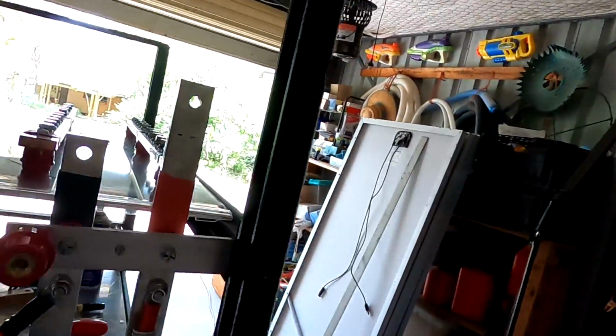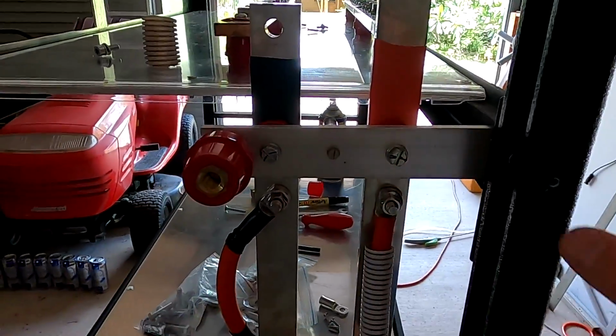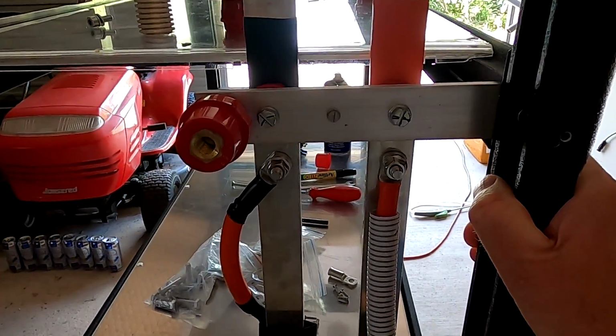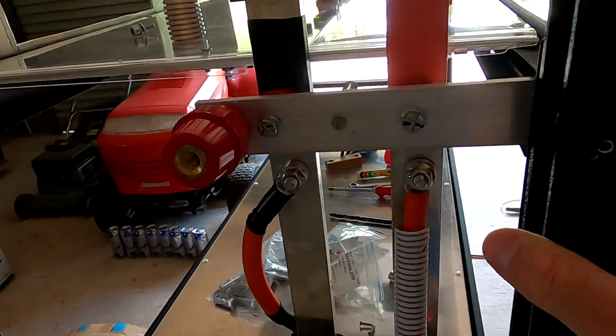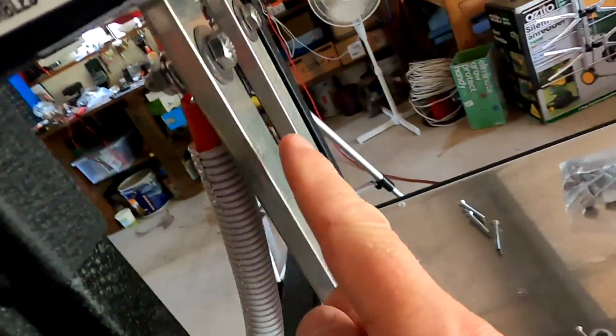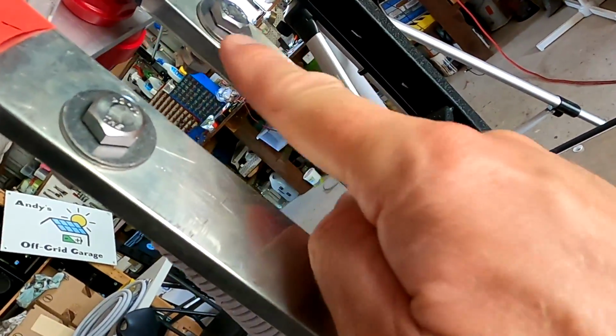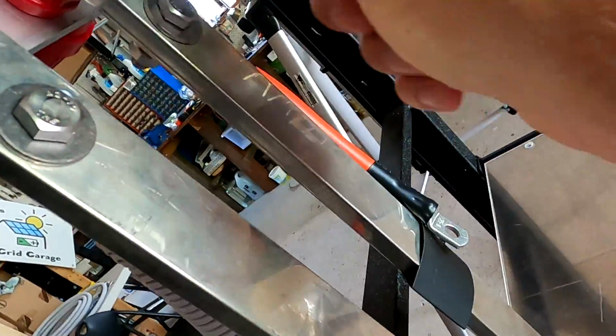I know this isn't the best design because we're crossing the other bus bar very closely, but there's not much I can do. I was thinking of having one cable on this side and the other on the other side, but there's just not enough room to bend the cable as needed to fit into the circuit breaker correctly. You don't want to put any sideways force on the ring lugs when they go into the circuit breaker—they should go in relatively straight.